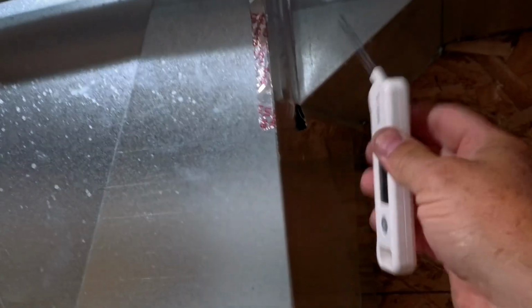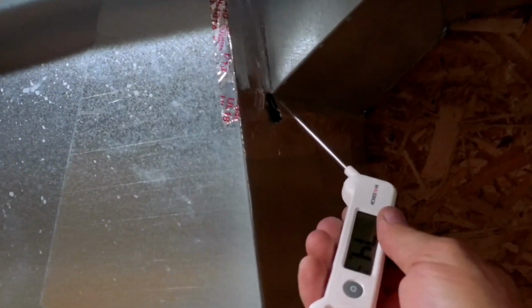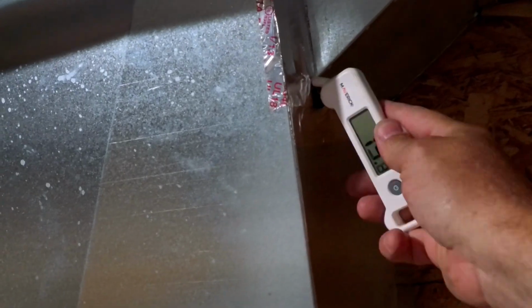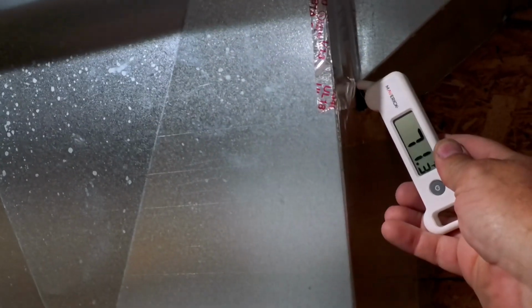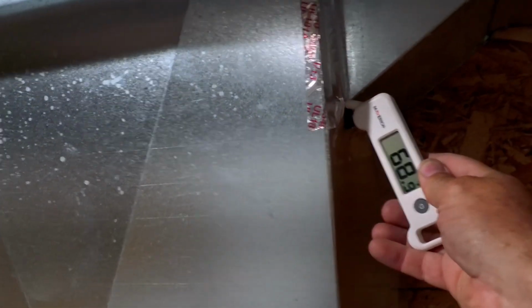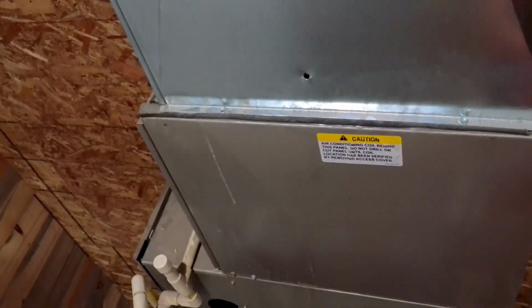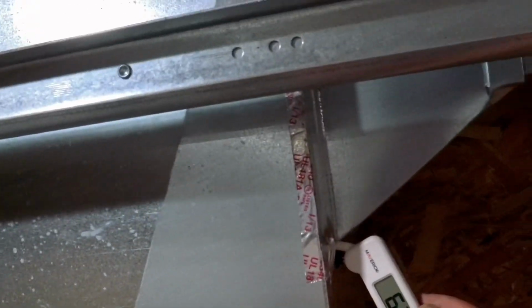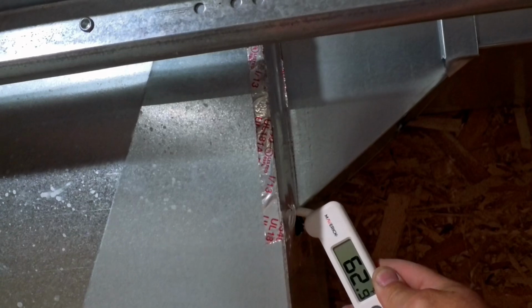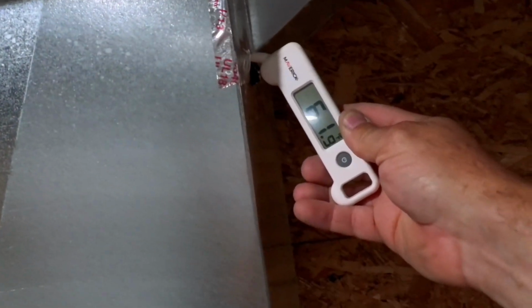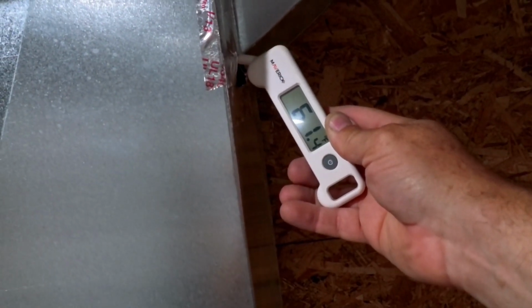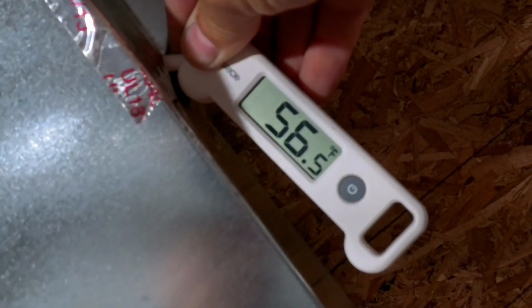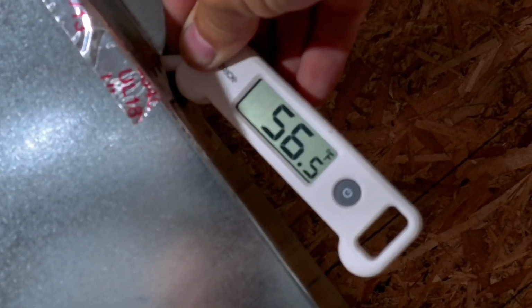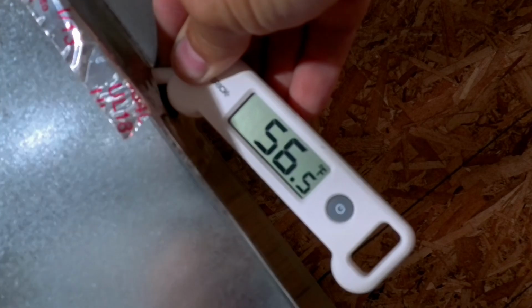So here at the first takeoff on my plenum, I know that there's an access right here in this corner that I left when I installed it. And if not, you can simply just drill a small hole or poke a hole in it with something. You don't want to do it down here at the A coil because you don't want to damage that coil. That's why we're going to go up here a good 4 foot at the takeoff, and we know there's nothing up here that's going to hurt anything. So now we're going to let the temperature settle, and then we're going to do some math. So as you can see on the thermometer, we're at about 56.5 degrees temperature coming out of the plenum.